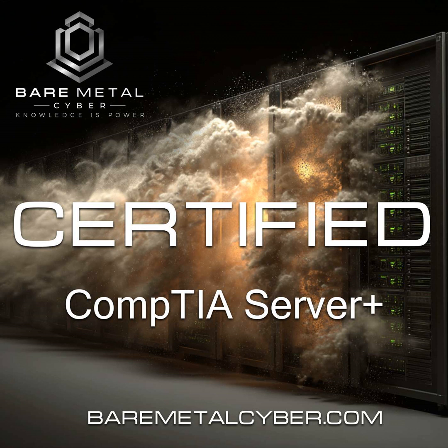The cooling strategy for each server form factor differs significantly. Tower servers rely on room air or built-in fans and don't usually require specific cooling design. Rack servers benefit from front-to-back airflow and are designed to match hot aisle and cold aisle patterns in server rooms. Blade systems need very precise cooling due to the density of hardware, often requiring dedicated airflow management, containment, or even liquid cooling. Server Plus emphasizes these thermal design considerations.